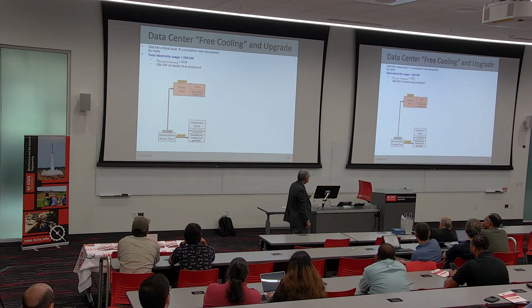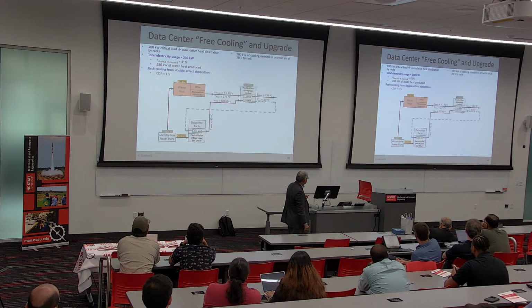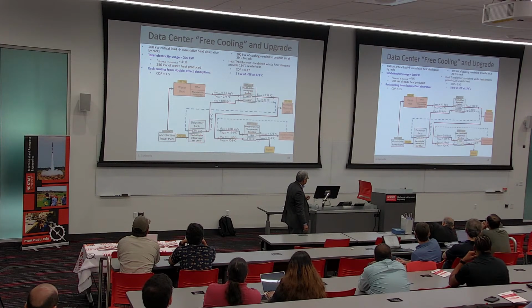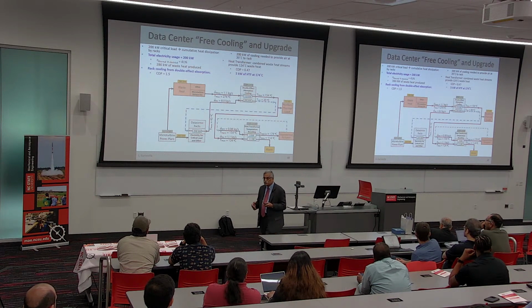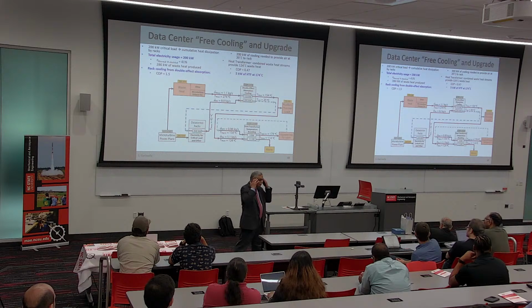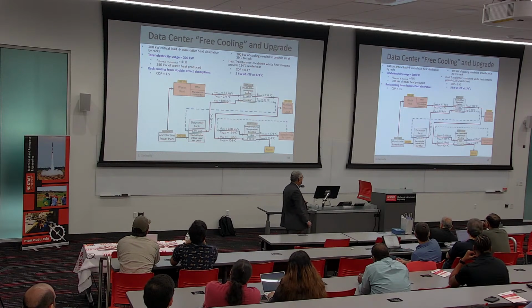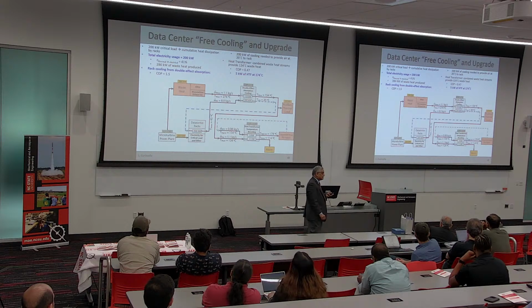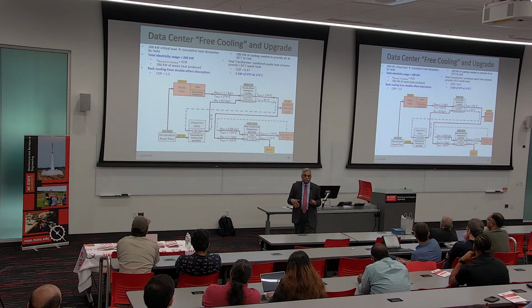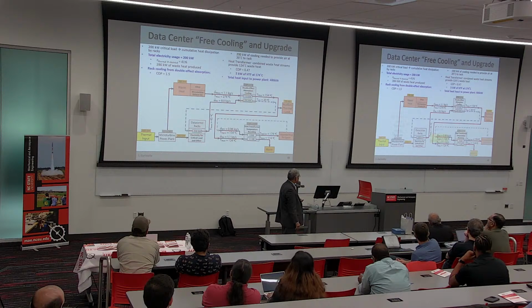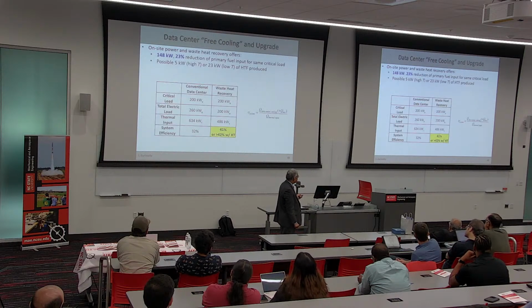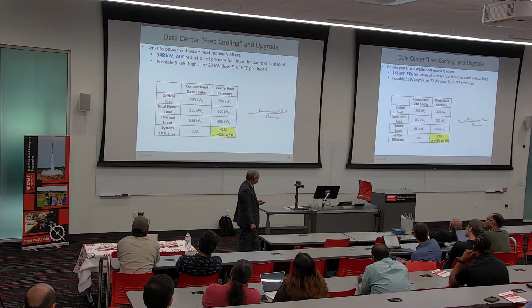And so this is what the balance becomes: you have this waste heat, and you use it to generate your cooling, and then you use a heat transformer to provide upgraded heat. So you're getting two useful end results, and with the vast amounts of electricity being used for data centers, these are some ideas that will reduce the overall energy footprint of data centers. Whereas the system efficiency may be 32%, we can enhance it all the way to about 41%, a significant improvement.